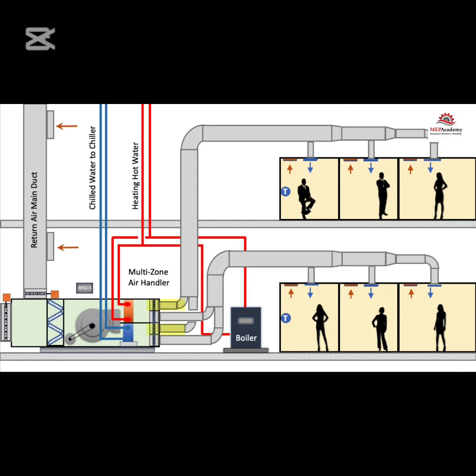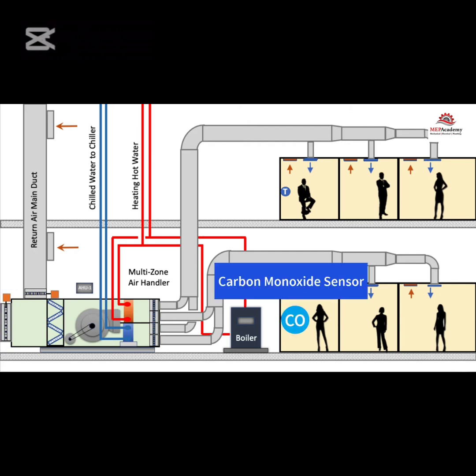This air handler has a mixing box that allows for return air and outside air to mix. The outside air damper will modulate to maintain the minimum amount of ventilation air as required by code. It's possible to control the outside air using a CO sensor in the space being served by this air handler to allow for energy conservation.